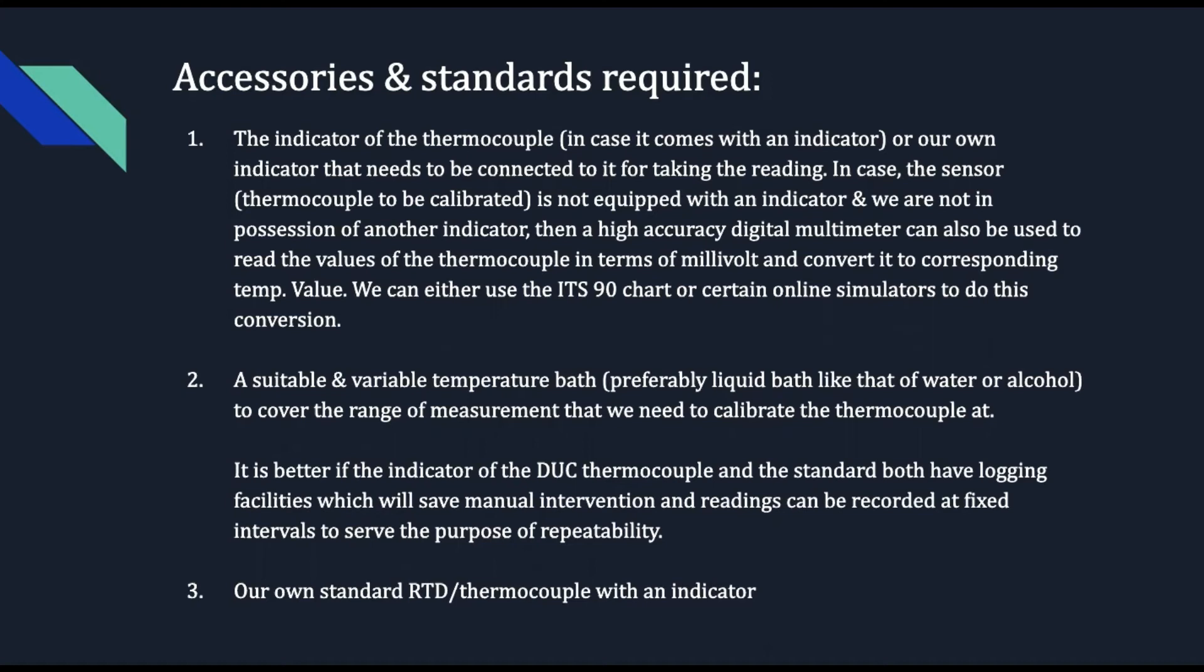2. A suitable and a variable temperature bath, preferably liquid bath like that of water or alcohol, to cover the range of measurement that we need to calibrate the thermocouple at. It is better if the indicator of the DUC thermocouple and the standard both have logging facilities which will save manual intervention and readings can be recorded at fixed intervals to serve the purpose of repeatability.